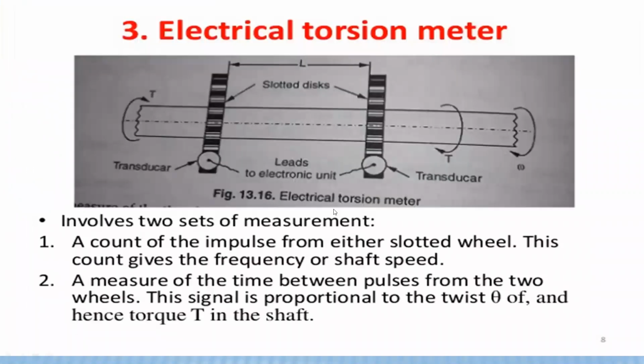Second one, it measures the time between the rotation of these two wheels. The signal is proportional to the twist theta and hence torque T in the shaft. These two signals, T and W, can be combined to estimate the power being transmitted by the shaft. Whenever the shaft is rotated, the shaft speed is observed using the slotted discs. This slotted disc gives the shaft speed, and these wheels are transmitting some amount of speed.